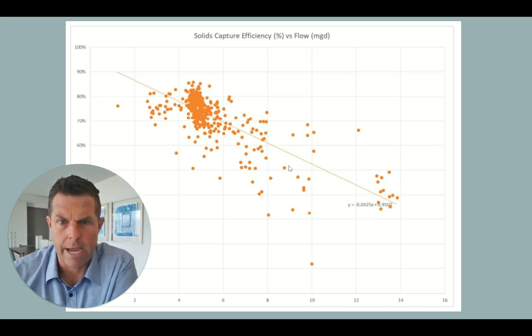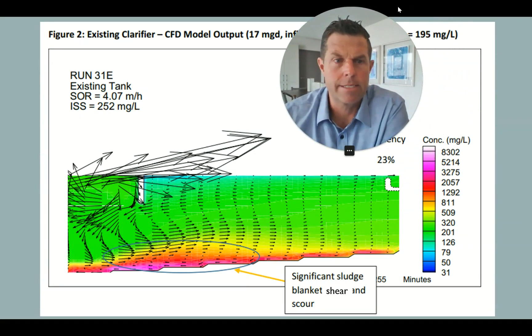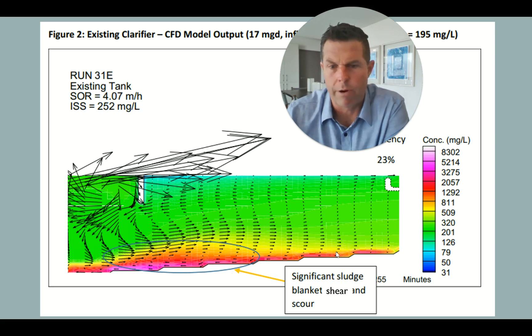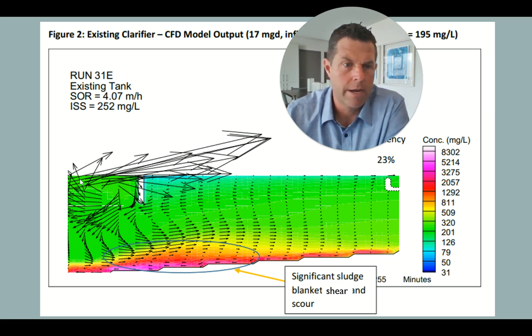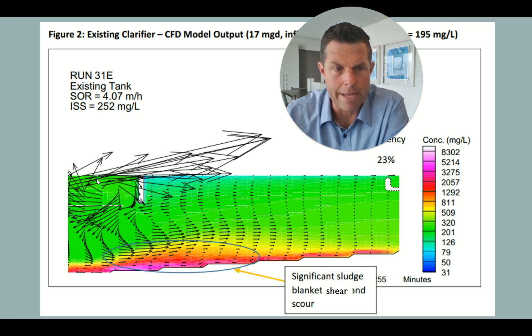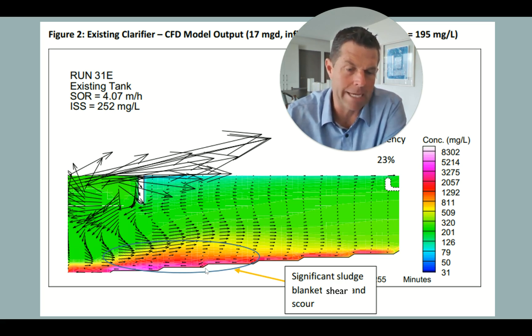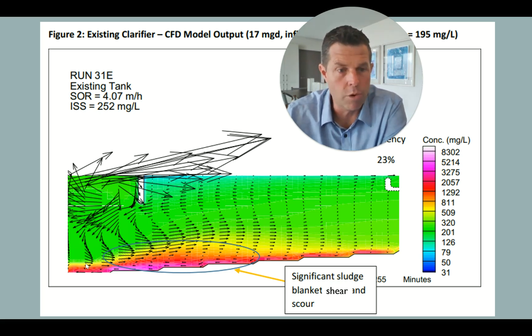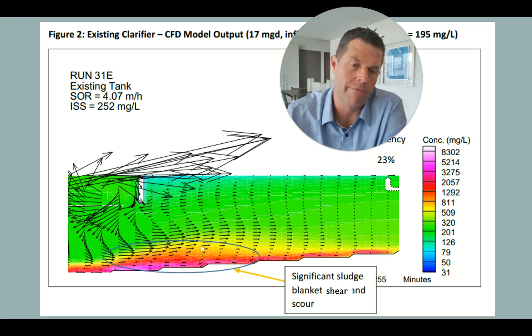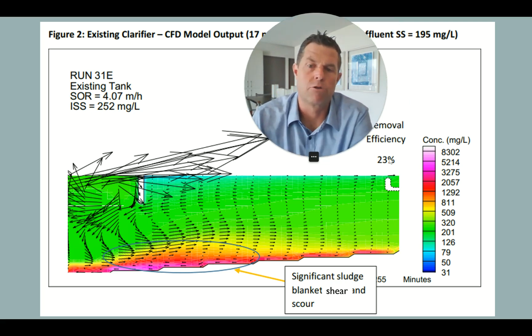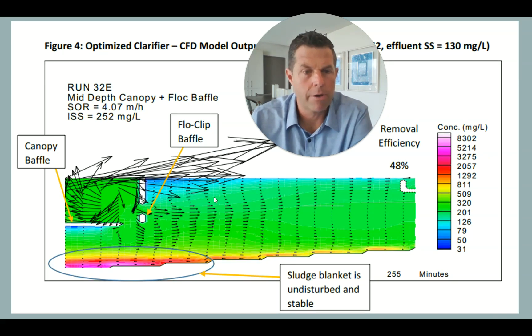We partnered with this agency and performed CFD analysis on the tank. Looking at the 95-foot clarifier in section — this is 47.5 feet — the flocculation well is here. From the center column, flow enters the tank, bounces into the floc well and is directed down. As we start pushing the loading up to 17 million gallons per day, those downward velocities press into the sludge blanket, and you can see this shearing action of the blanket. In a tank where you're trying to draw sludge inward into the sludge hopper, this shear is self-defeating. Above a certain flow rate, the solids capture in this tank is low — both the historical data and the modeling predict a solids removal efficiency of 23%.